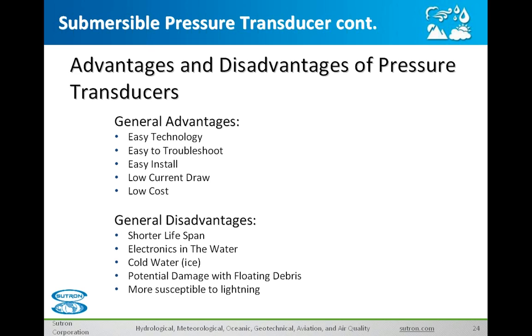Gary asked whether a pressure transducer lasts longer in a groundwater application than a surface water application. Paul confirmed: yes, that is typically the case — you can protect them a lot better. They are sensitive devices, so they need to be mounted and fixed to something because banging around will affect calibration and lifespan. In groundwater, they do tend to last quite a bit longer. Paul agreed that in a surface water application, you should probably look at other alternatives, though they do work as long as they're submerged below the surface of ice. They don't work very well when they get iced over, and the sensitive device can be damaged.